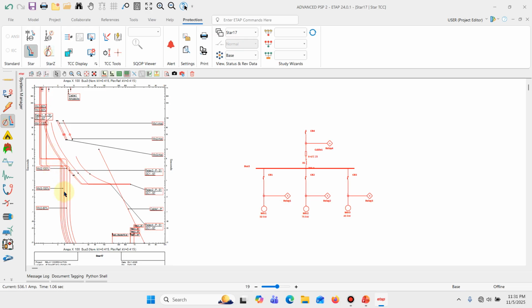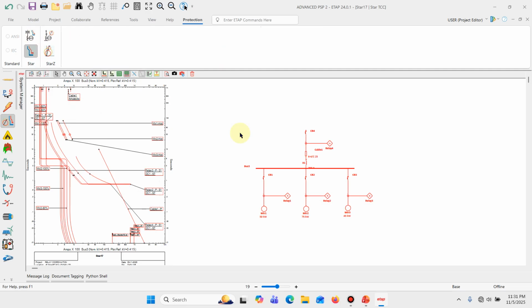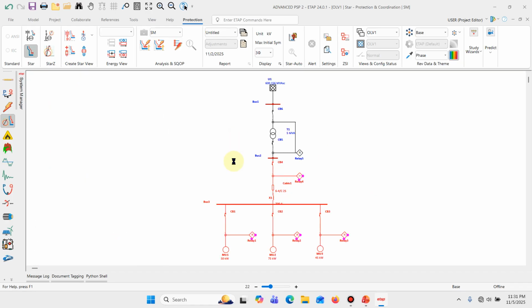So we can see our motor starting curves, we can see our relay curves, we can see the motor damage curves. So from this TCC, can we tell, is our system properly coordinated? Is it properly protected? You can take a wild guess. But let's not jump into conclusions. Let's simulate. That's what the software is here for. So let's say I insert a fault at any of these. Okay, let's use this motor. We have a fault on this motor.